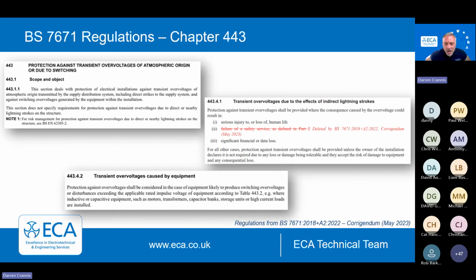Where do we need them? Very simple. It's a risk assessment. So we're not going to dwell on this too much, but when you perform a risk assessment and that is required, then you'll install SPDs accordingly. It's important to get that right. Where a risk assessment says that you don't require these, then you won't.